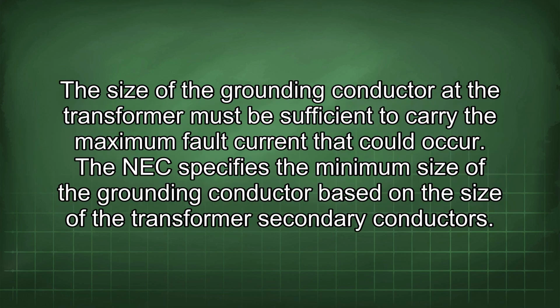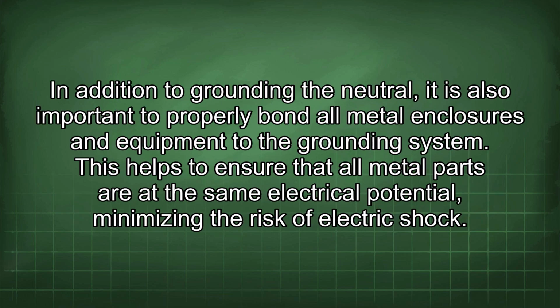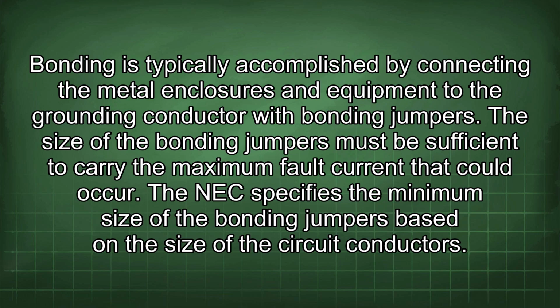The size of the grounding conductor at the transformer must be sufficient to carry the maximum fault current that could occur. The NEC specifies the minimum size of the grounding conductor based on the size of the transformer secondary conductors. In addition to grounding the neutral, it is also important to properly bond all metal enclosures and equipment to the grounding system. This helps to ensure that all metal parts are at the same electrical potential, minimizing the risk of electric shock. Bonding is typically accomplished by connecting the metal enclosures and equipment to the grounding conductor with bonding jumpers. The size of the bonding jumpers must be sufficient to carry the maximum fault current that could occur. The NEC specifies the minimum size of the bonding jumpers based on the size of the circuit conductors.